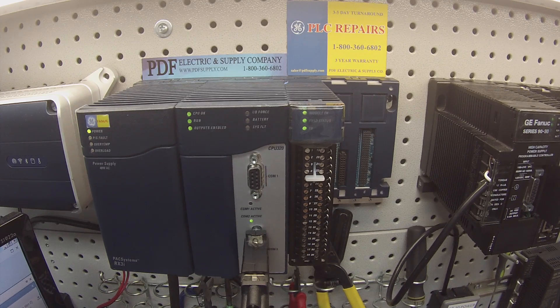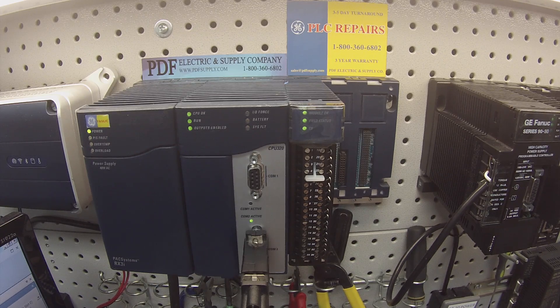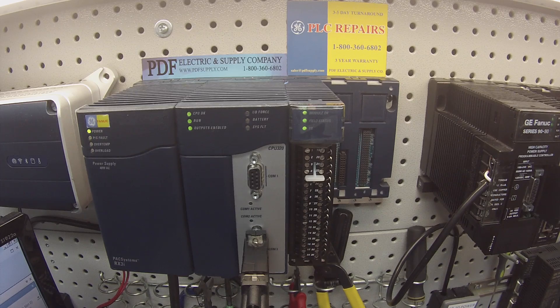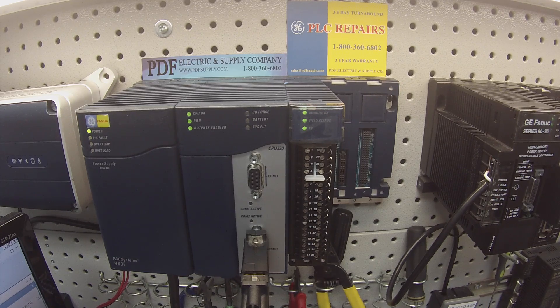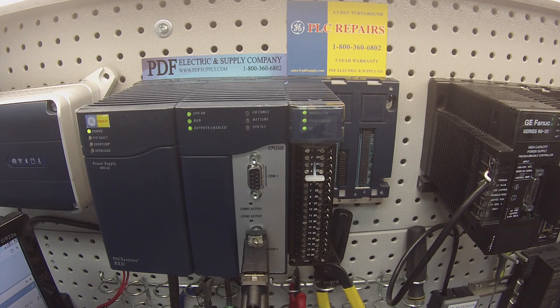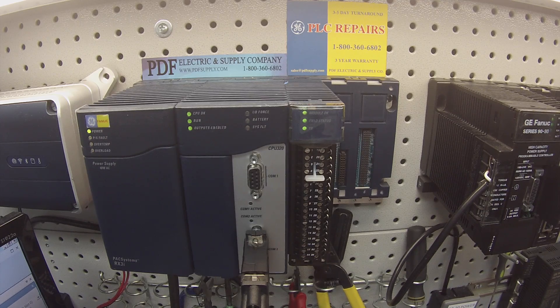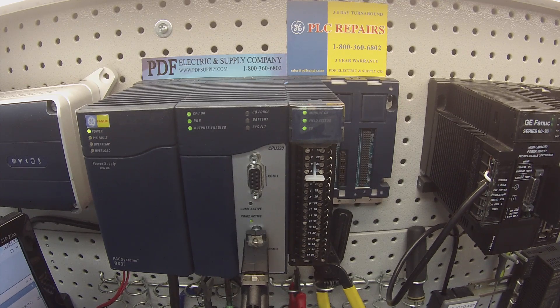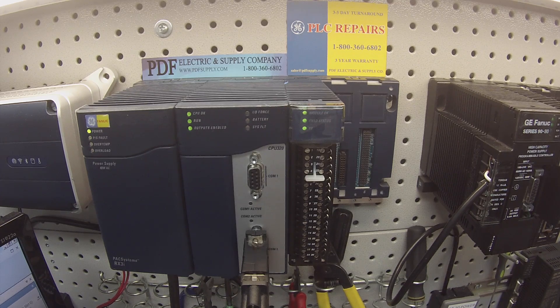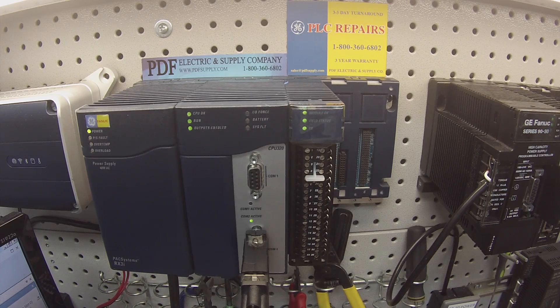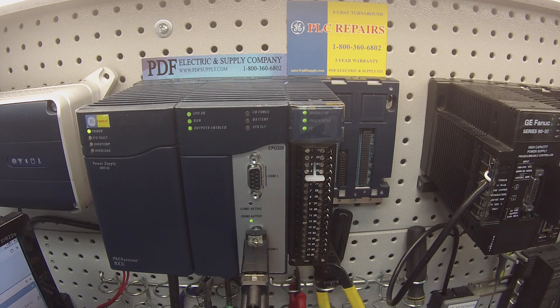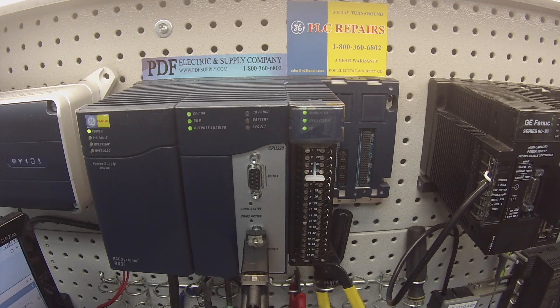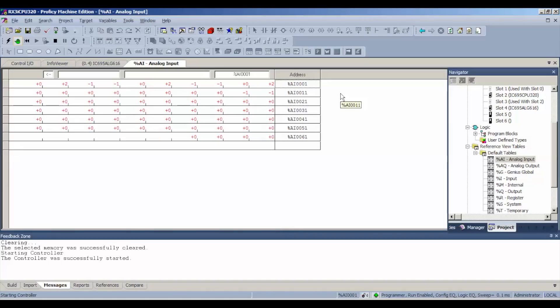Sometimes they fail at full value, as if the values come at its max. You can also use a 10 volt power supply that's variable from zero to 10 volts. If for some reason you want to check it in negative 10 volts, going from negative 10 volts all the way to zero volts or positive 10, you can simply change your leads so that your negative probe is now the lead that you would touch to each channel.